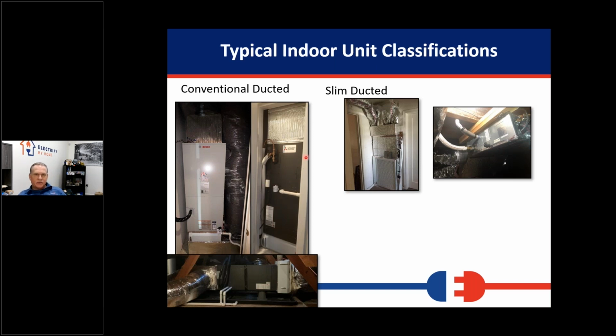Some of these slim ducted units can actually be installed vertically. Not every model can do that, because it requires a different type of drain that allows condensation to leave in two ways. But we can take a small alcove, like we did in this house, and use that space to put a system in.